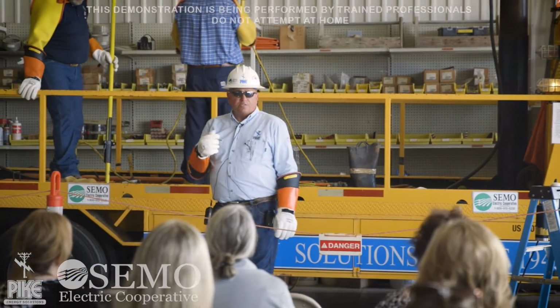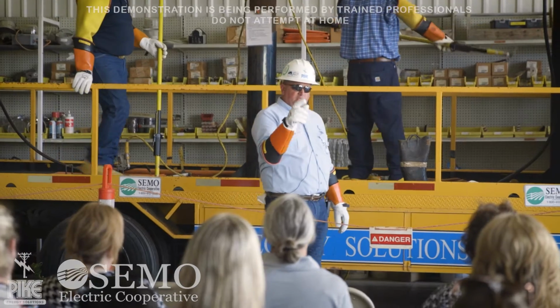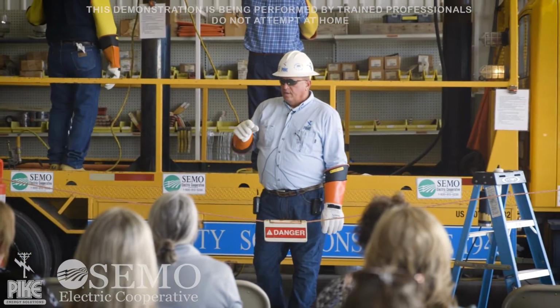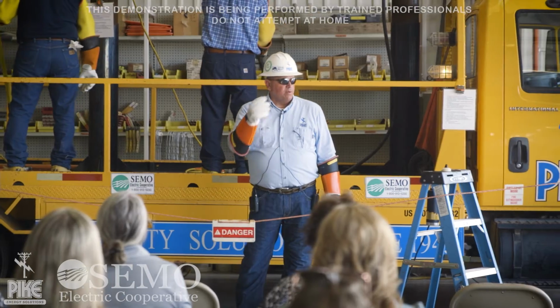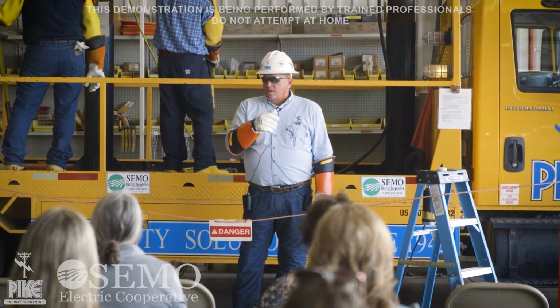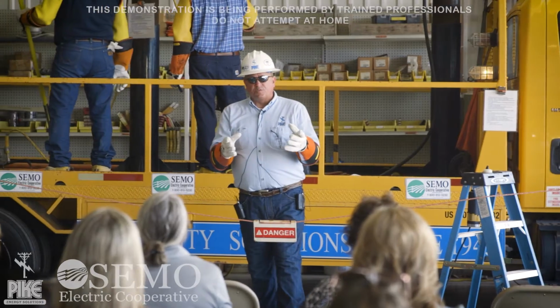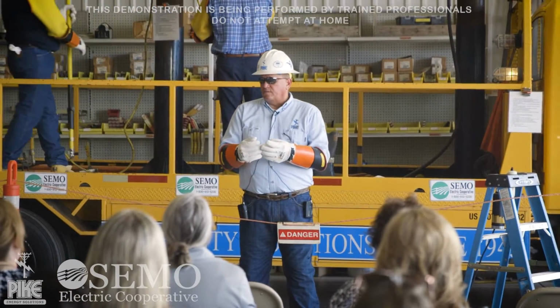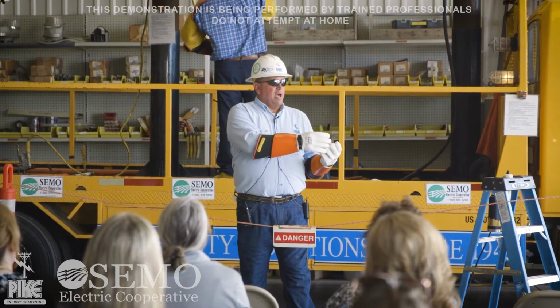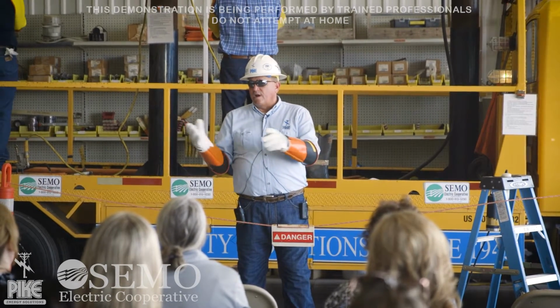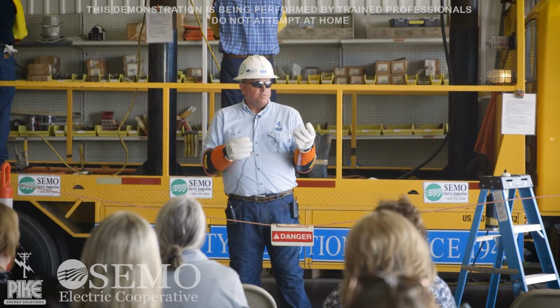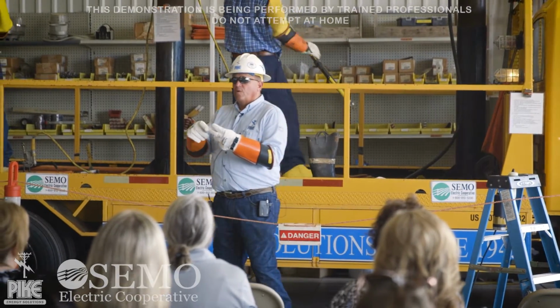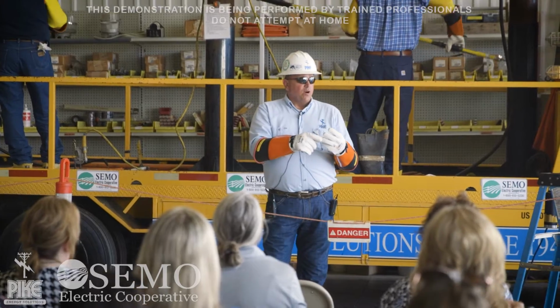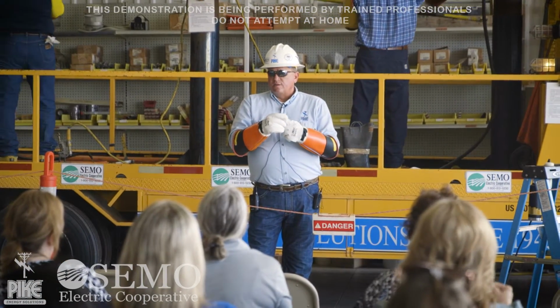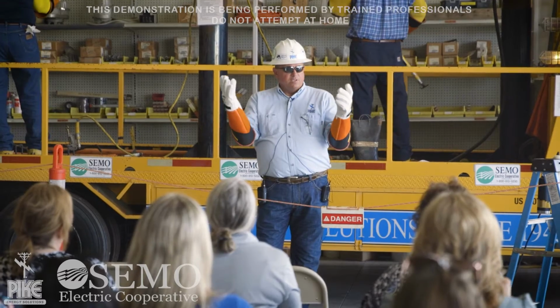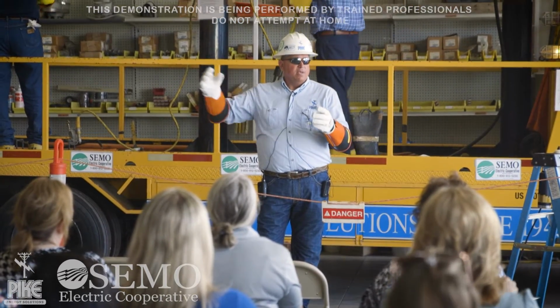We do a lot of storm restoration work here at Pike. Matter of fact, we're moving crews today over in the Cincinnati area, different areas of the company working on some outages over there. But here, in this industry, there's a term called flag, tag, and ground. There's also a term called lockout, tag out. Basically the same thing, but in our industry, it's called flag, tag, and ground. There's 4 things that must take place before a line or a conductor can be worked as de-energized. Number 1 is a visible opening. We got to have a visible opening between the work location and the source.